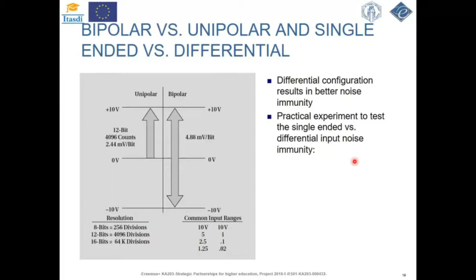If we compare the single-ended, or ground-reference, configuration with the differential input, we can observe that the differential setup will usually offer better noise immunity. This is especially important in systems that use data from a number of different sensors, especially if they're located at a long distance. Now I would like to show you a practical experiment that can test single-ended versus differential configuration with respect to noise immunity.